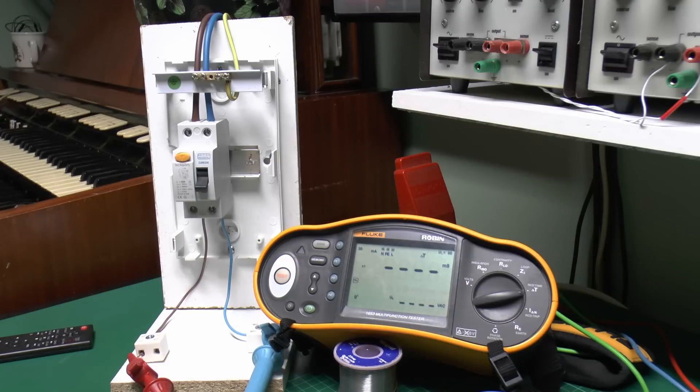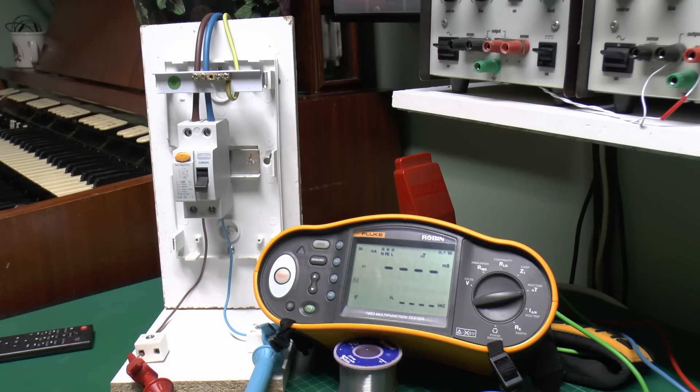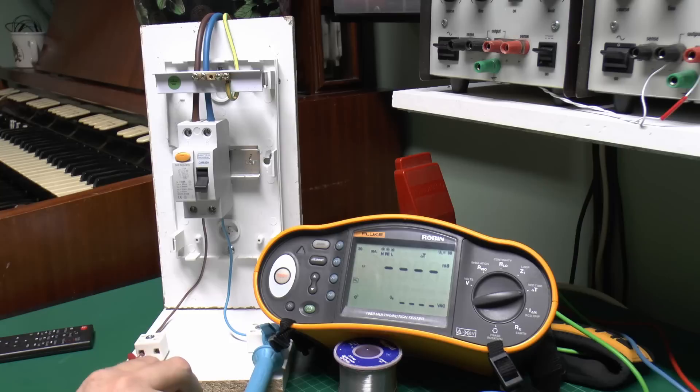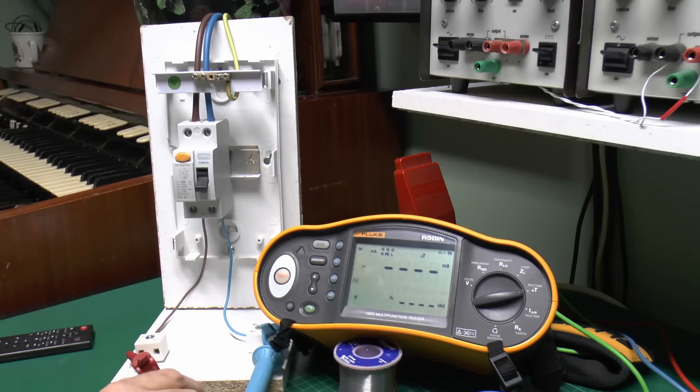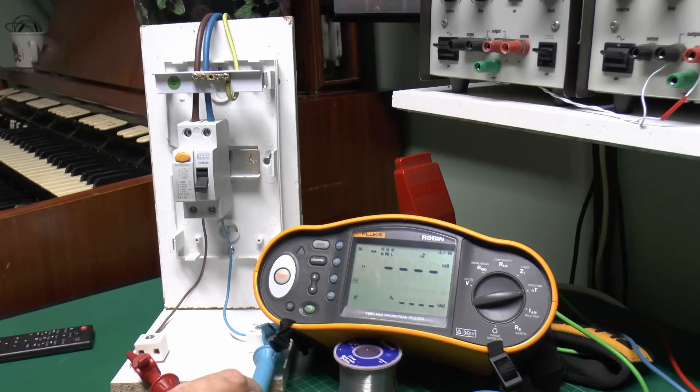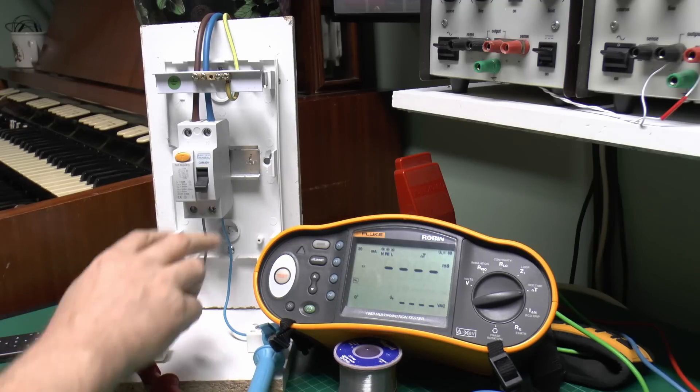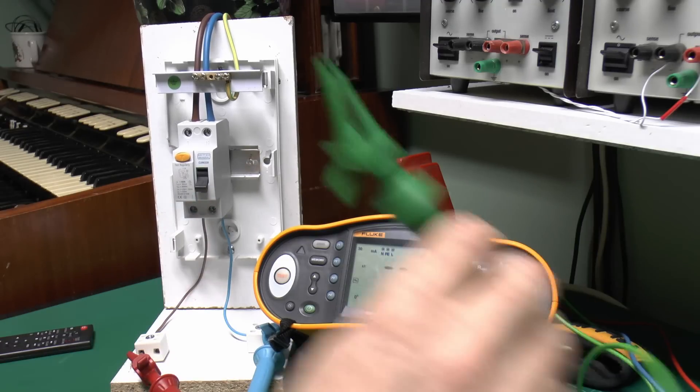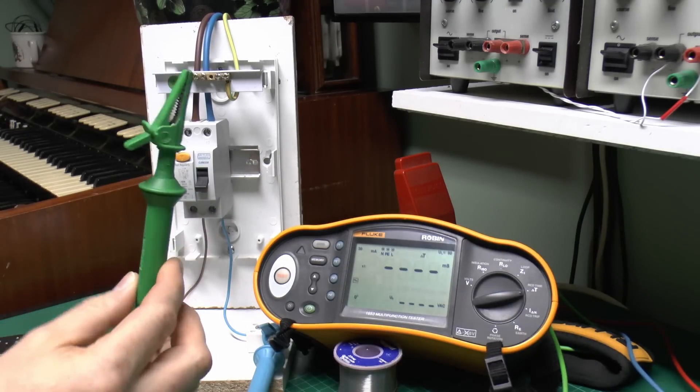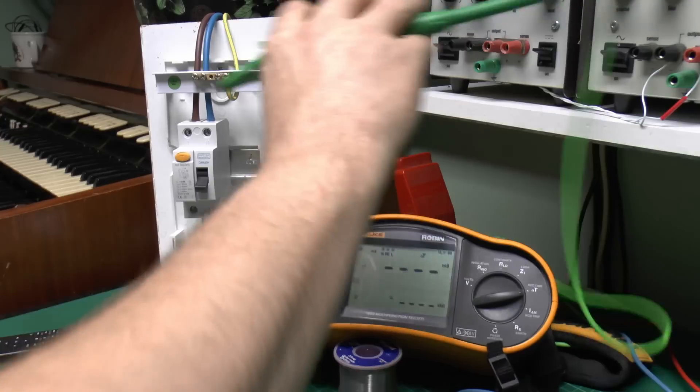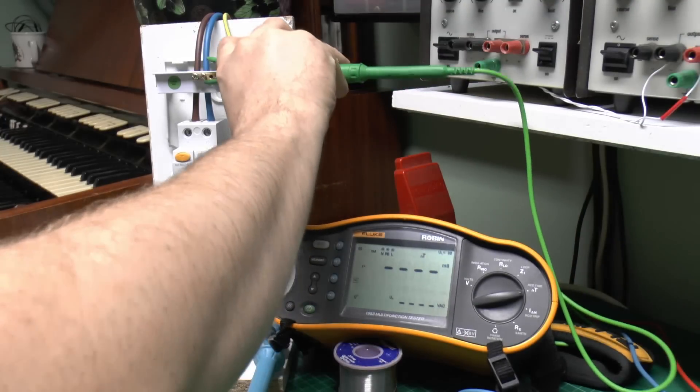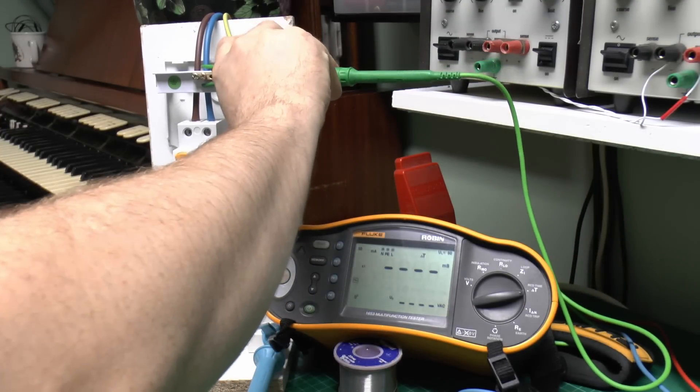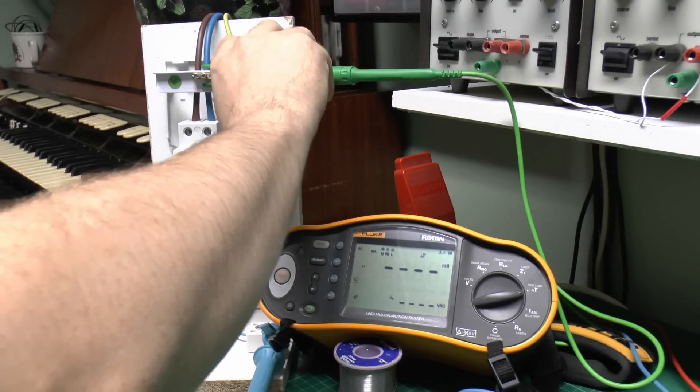Now the first thing to do, of course, is connect the correct test leads to the equipment. So we've got the line over here on this red lead, neutral here on the blue, and notice these are on the outgoing side of the RCD. And the earth wire, or the earth lead here, which is this green one, of course connects up to the earth terminal at the top here.